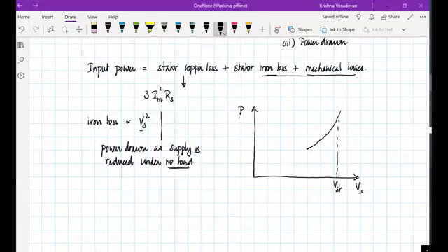So you do this experiment until you get a substantial variation in the input active power drawn, and then what you do is you extend this to meet the y-axis, and it is then assumed that the intercept that happens here is equivalent to the mechanical losses, whereas the decrease that is happening here, all along, is due to the iron losses that are happening.